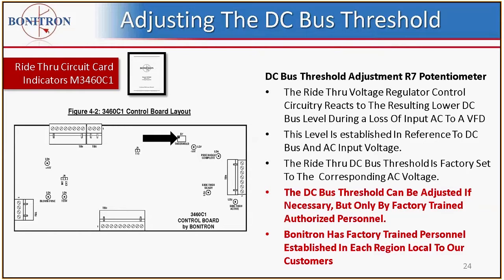The ride-through DC bus threshold is factory set, and once again it is in correlation to the corresponding AC line voltage, which varies throughout the world. The DC bus threshold can be adjusted if necessary, but only by factory trained authorized personnel, and as I mentioned earlier, we have global facilities that can handle this. And we can also provide information and training to specific companies that feel that this has to be accomplished.